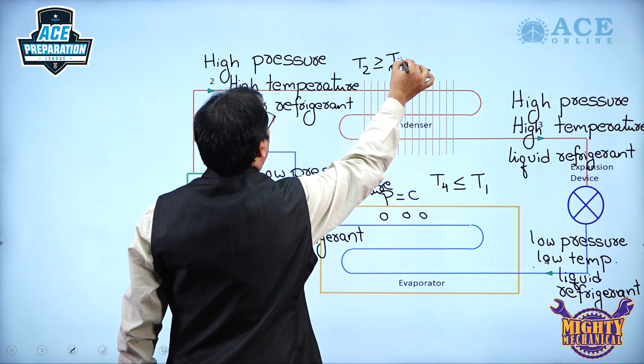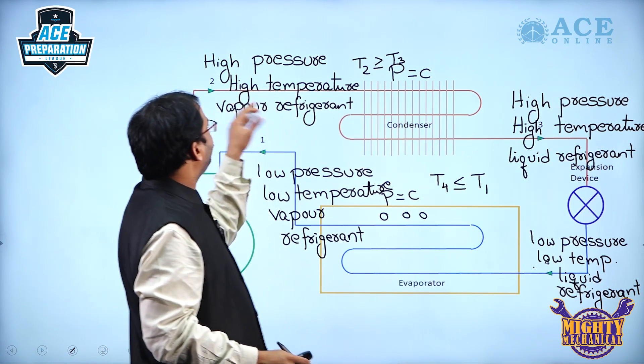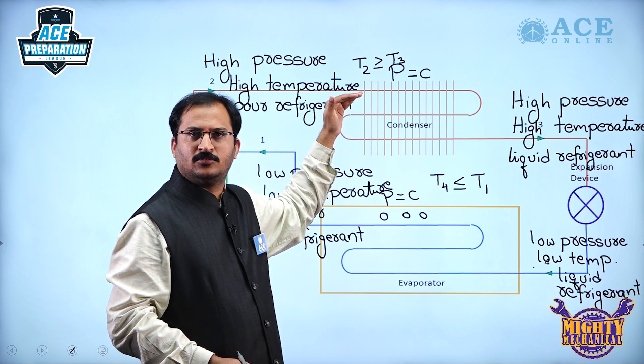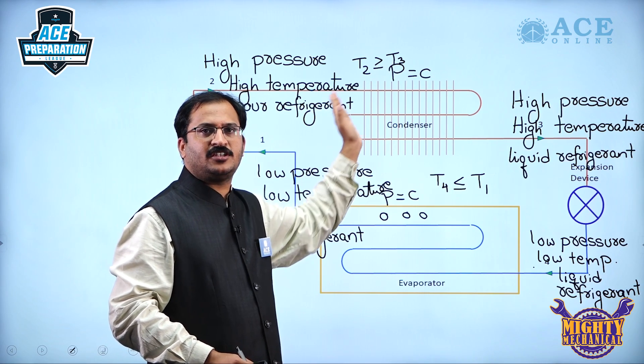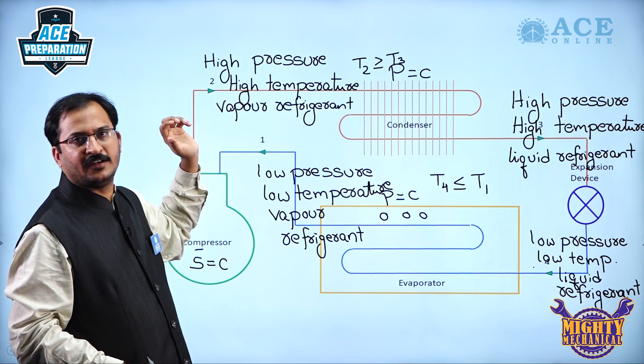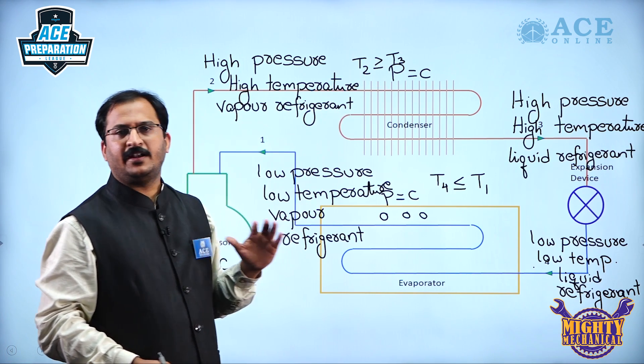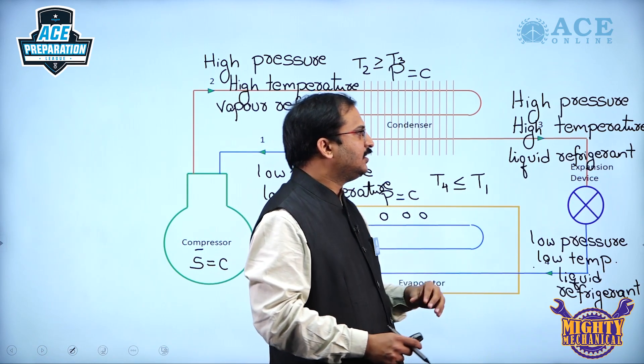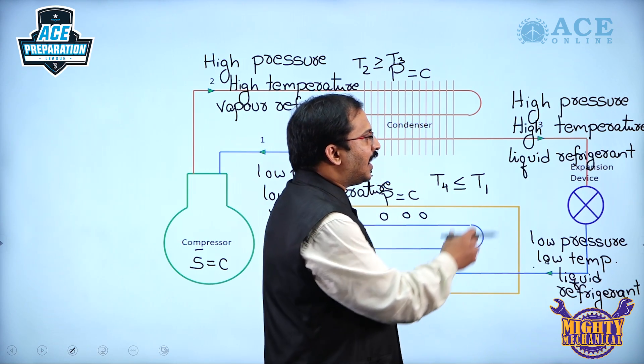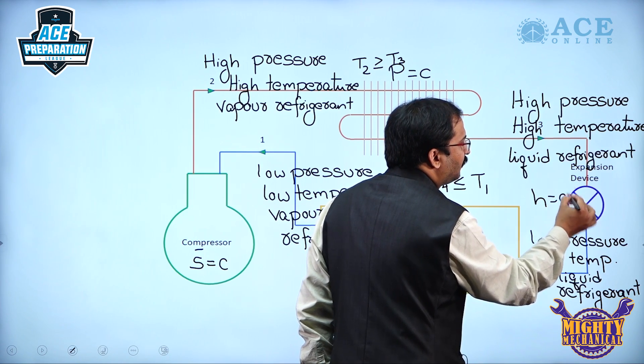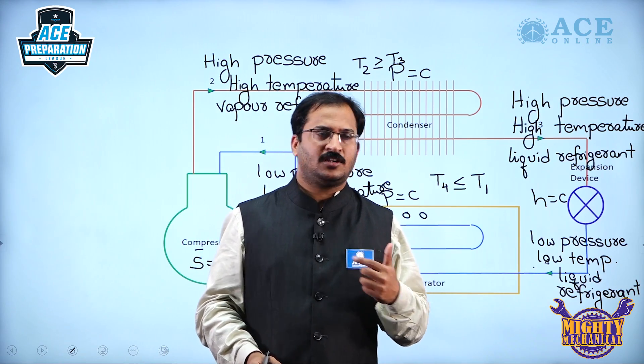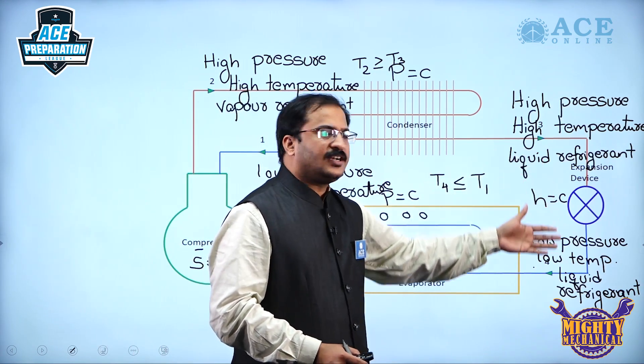T2 will be greater than or equal to T3 because the condition entering the condenser may be superheated. From the superheated state to the saturation state the temperature drops, and at the saturation temperature phase change takes place. In the expansion device, high pressure high temperature liquid refrigerant gets converted into low pressure low temperature liquid refrigerant, and during this expansion enthalpy remains constant — this is throttling. There is a drop in pressure and temperature, and it is considered an irreversible process.